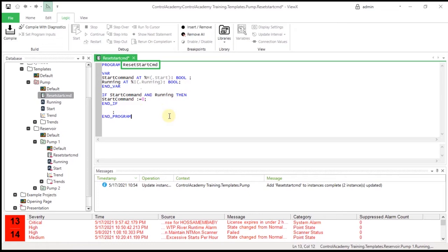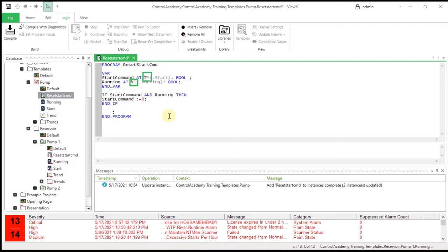The Reset Start CMD part of the line is the identifier. The identifier names the element within the program and usually describes the purpose of the program. It must be an alphanumeric string that begins with a letter. It cannot contain adjacent underscore characters or spaces. The statements between VAR and END_VAR are the variable declarations, which tell the program which objects and properties in the database should be used in this program.